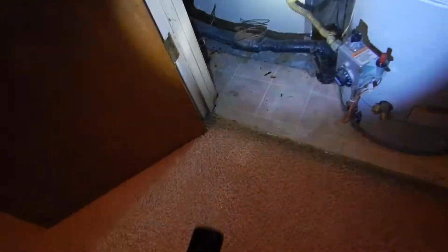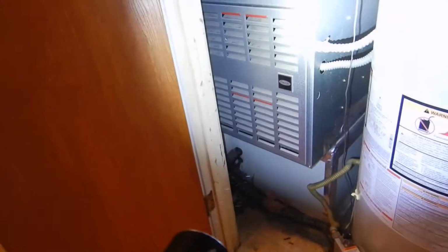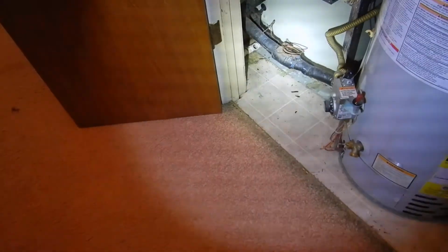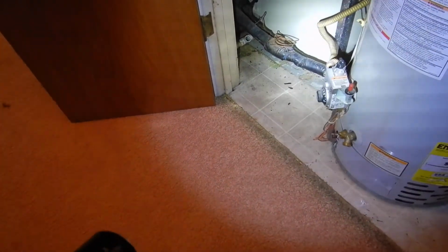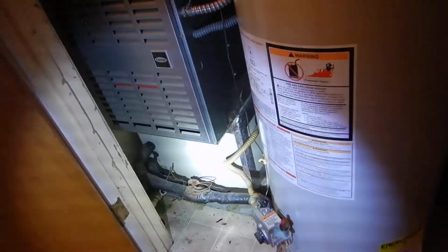Okay, these doors should be sealed like exterior doors. You shouldn't be getting your combustible air from underneath here. You've got a gas water heater, you've got a gas furnace. If it spills carbon monoxide out, then it gets sucked back up in. That's not the return air. Never mind. I get carried away. I think it still should be sealed, but not for the same reasons.